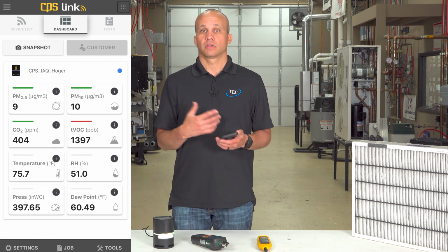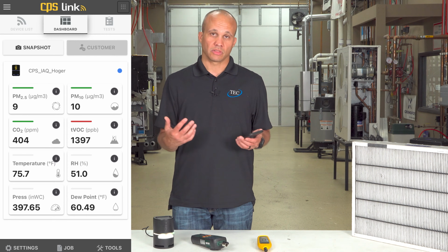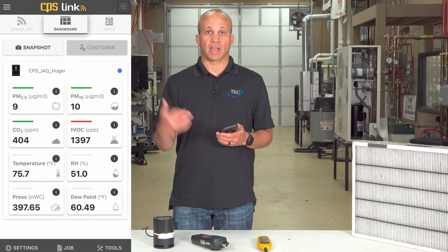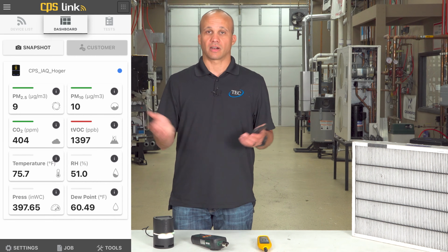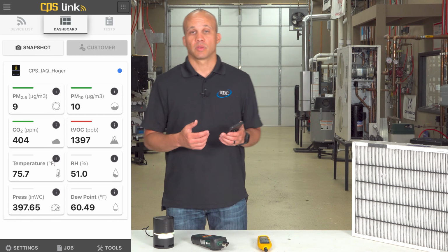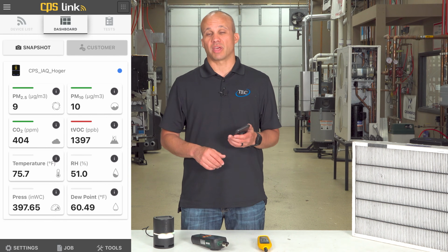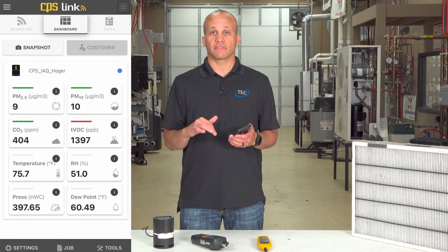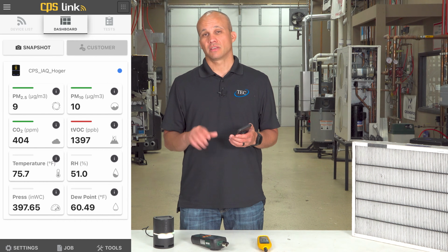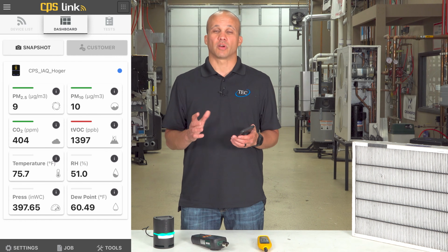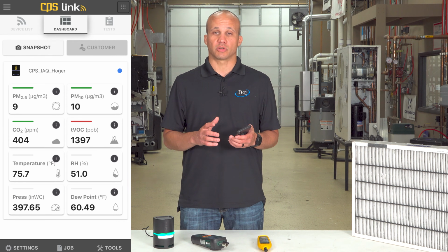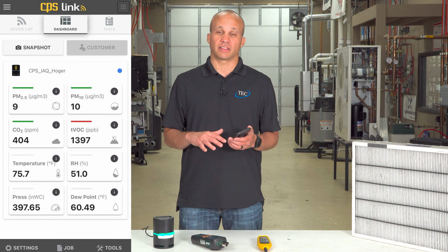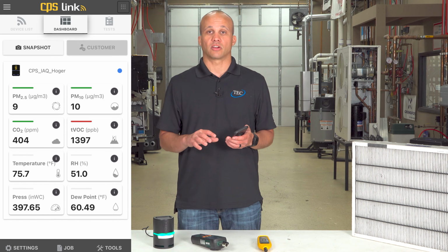It's like 400, which makes sense because we're in a giant room. There's only two of us in the room and we had the door open for a while. So outside air kind of came in, right? But if it starts getting higher, you specifically want to pay attention to it. Usually we say 700 parts per million above the outdoor levels, which are usually like 400, 450. So let's just say for a check figure, if you're above 1,200 parts per million of CO2 in a space, you're probably under-ventilating the space and you need to address that in your building.